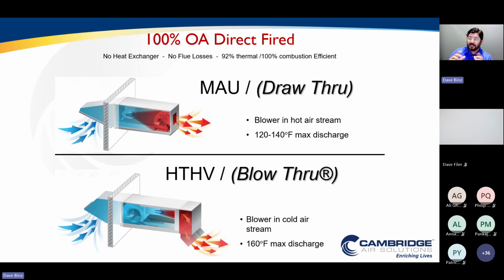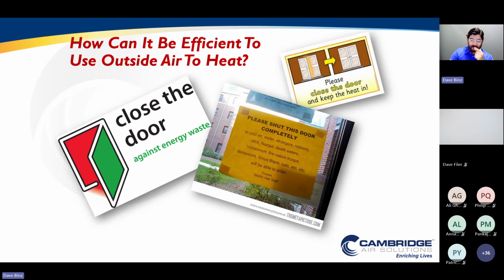But when we talk about HTHV, we do one simple thing: we move the blower upstream of the burner. We put the blower in the cold airstream. So now I'm pushing, or blowing, that air through the burner, and my motor and bearings are in the cold airstream. With that, I can increase my discharge temperature, so I can get more heat in a lower volume. I get more heat into a smaller box. And so I can do more space heating where my ventilation requirements are a little bit lower, which is what we often see in warehouse spaces.